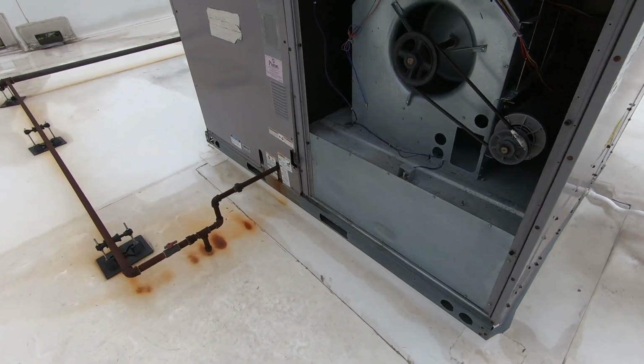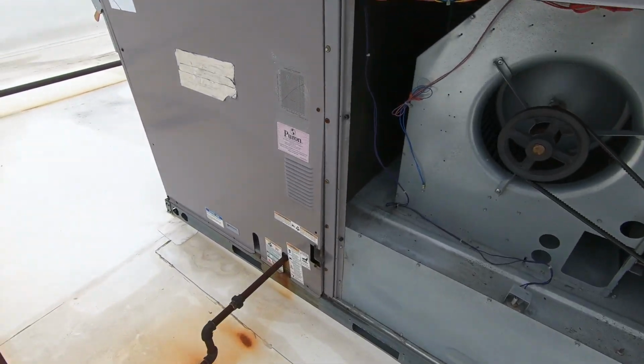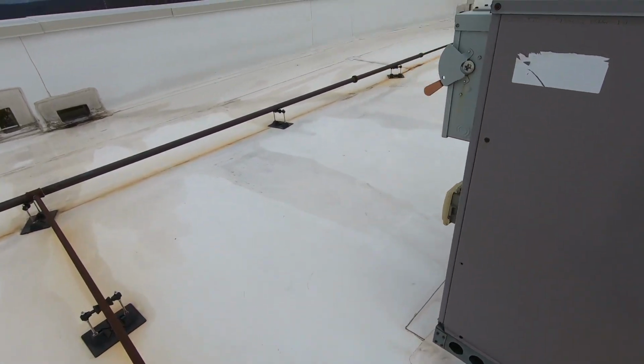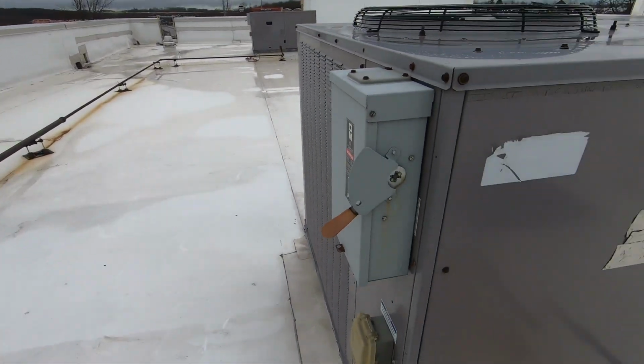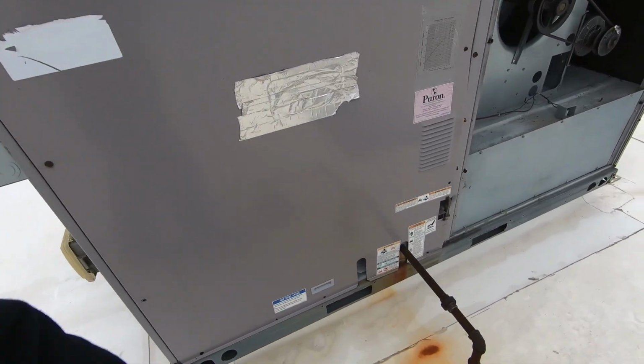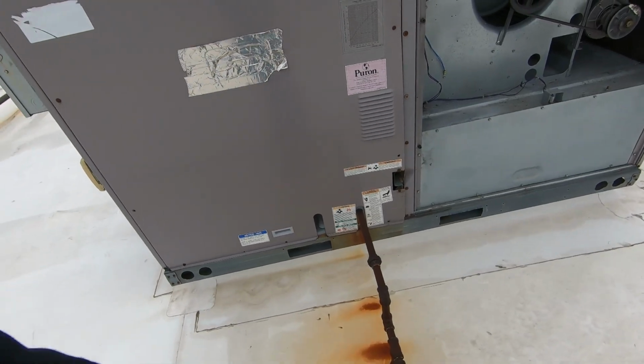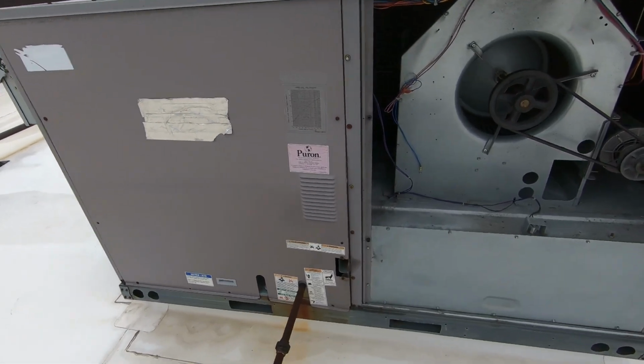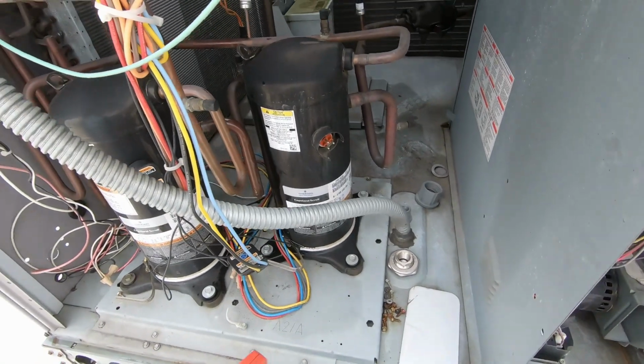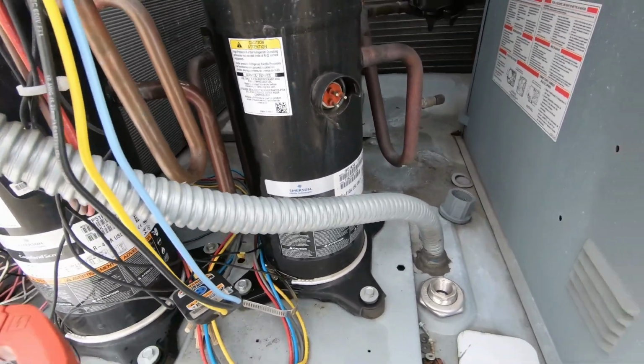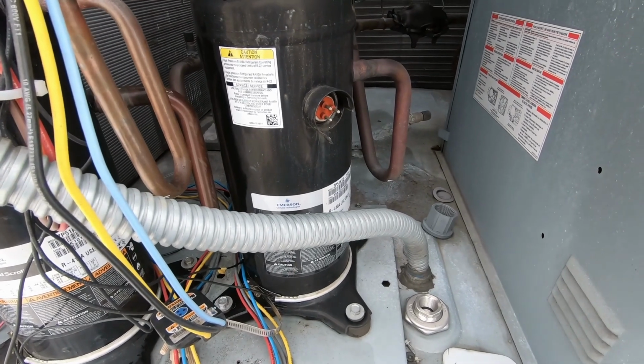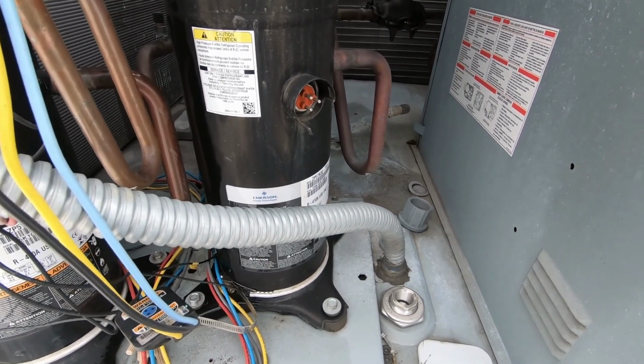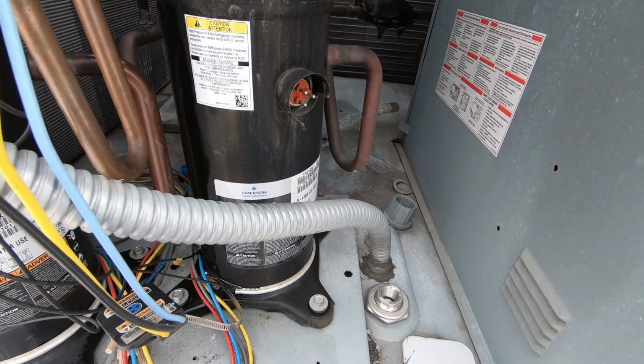I'd say 50-50 actually with these Carriers. So I got the power off. We're gonna open this one up, give it a quick look, make sure it heats, make sure it's safe. Maybe the rollout switch is bypassed on this one. I don't know. I got to look at it. All right, well, right off the bat, I've got a compressor plug pulled. Looks like the rollout switch is properly wired.